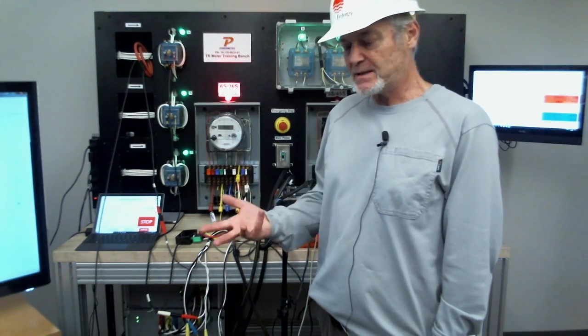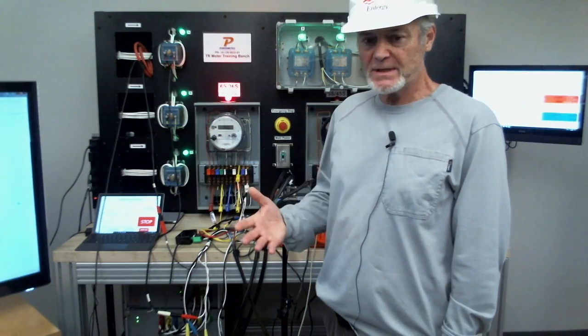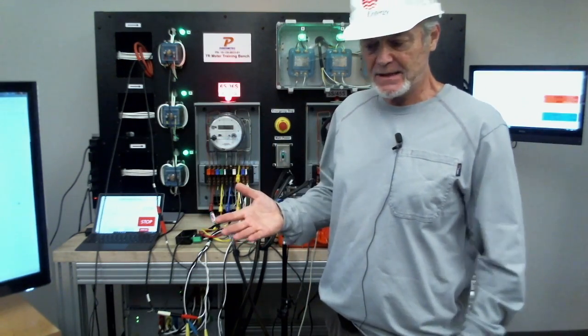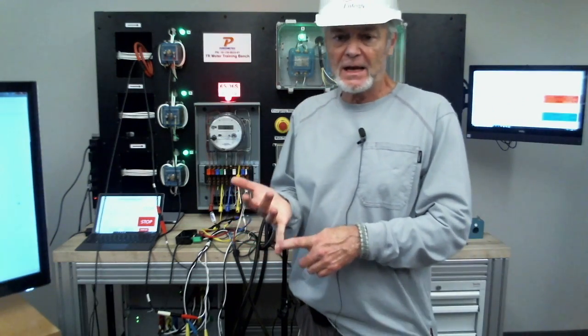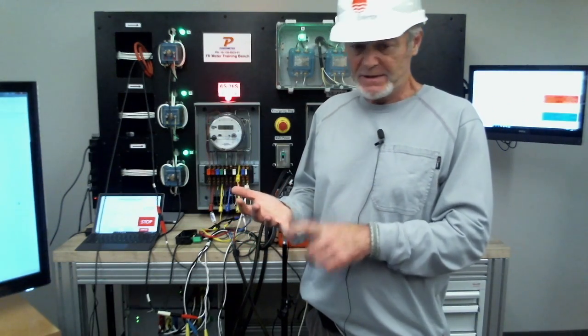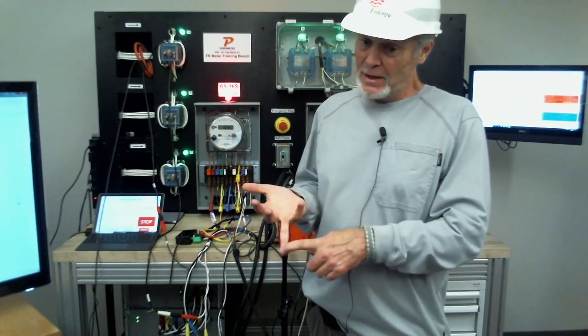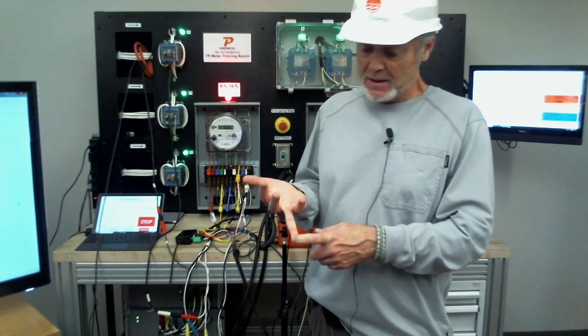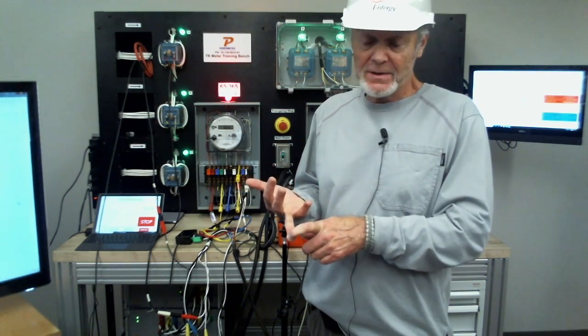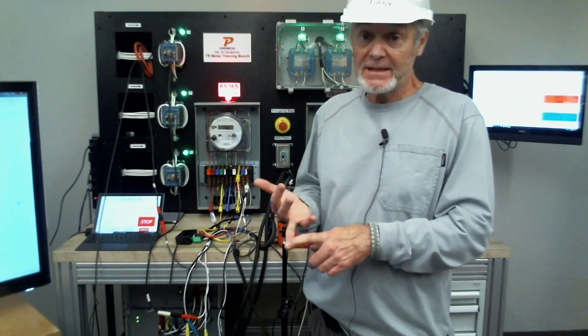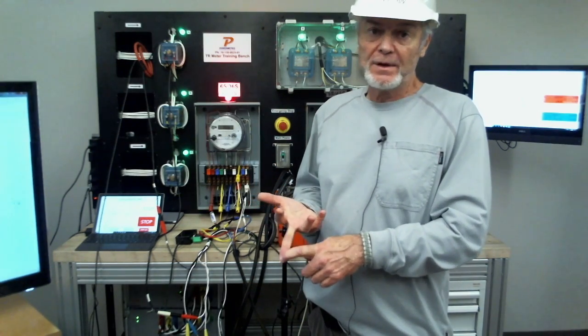What we're talking about today is doing a load boost test, which is when you show up at a site and there's not enough load to do the test. We know CTs do not like to be underloaded, they don't test well at all. Actually, according to ANSI, they have to have at least 10% loading on them. So a 400 to 5 CT has to have at least 40 amps on it for it to be a legitimate ANSI test.